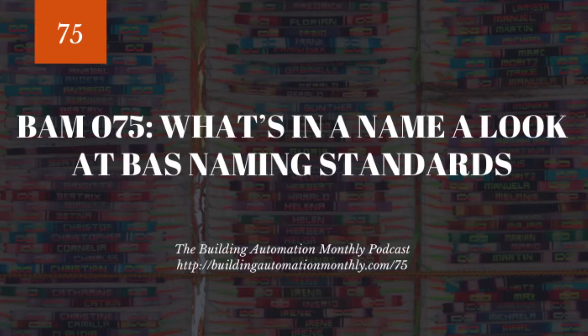A bad naming standard is not going to give you any context to what is going on in your building. So in one building, you may have a floor where they're VAVs, and then another would be where they're boxes, and then something else would be their spaces. And you just got all sorts of different names, and it's zone temp, space temp, room temp, just temp. Sometimes discharge temp and zone temp are just called temp, and then you're like, okay, which temp? Is it discharge temp? Is it zone temp? Is it supply temp?